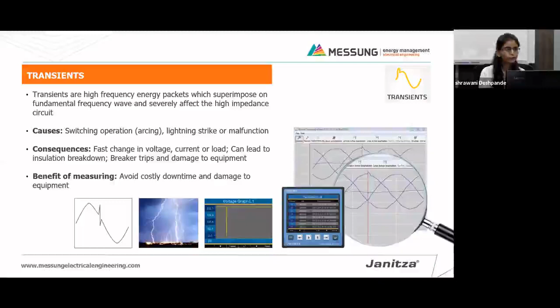Now, the consequences of transients include damage to the equipment or breakdown of the insulation. Though breakdown of insulation is not a sudden consequence, it might happen after a certain duration of time due to continuous hitting of these transients. As I said, a transient occurs within a very short duration of time, so in order to capture these transients, you need continuous monitoring of your system. You also have to use a meter with a high sampling frequency, so that you are able to capture those transients.